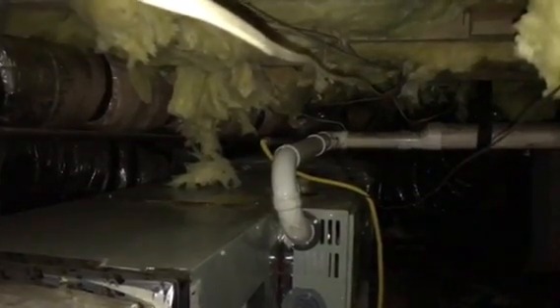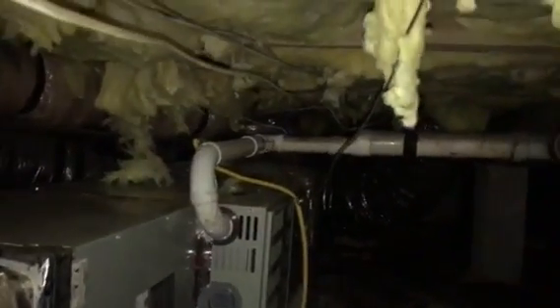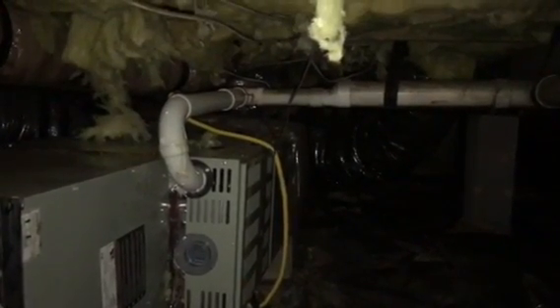But you can see this thing makes 2 U-turns that it really doesn't have to make. So I believe that's why we were able to make a difference just by taking that restriction off the end of the pipe. But anyway, we do have them heat, and we do see what's going on, and the product is not letting me down. It's the installation. So lesson learned, and move forward, and thanks for watching.